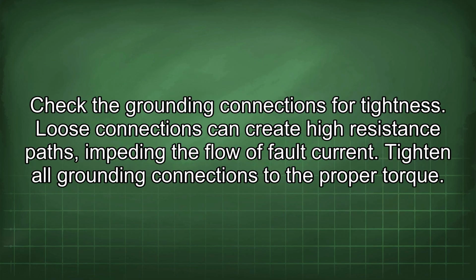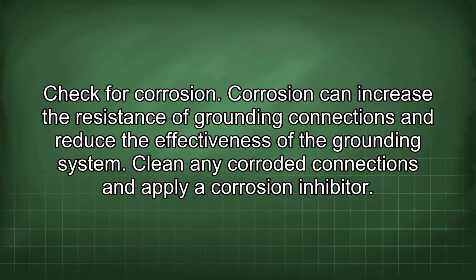Check the grounding connections for tightness. Loose connections can create high resistance paths, impeding the flow of fault current. Tighten all grounding connections to the proper torque. Check for corrosion. Corrosion can increase the resistance of grounding connections and reduce the effectiveness of the grounding system. Clean any corroded connections and apply a corrosion inhibitor.